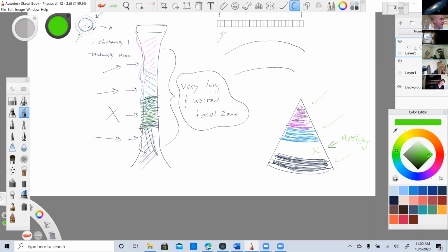Shape of the two-dimensional image. This is what it's going to look like on our screen. It's going to be fan or pie or sector shaped. Consequences of a damaged or malfunctioning active element. We get dropout on our screen. It goes right to left, left to right. Okay.